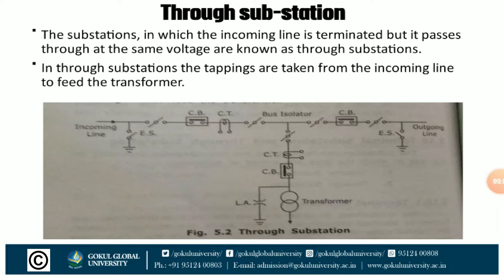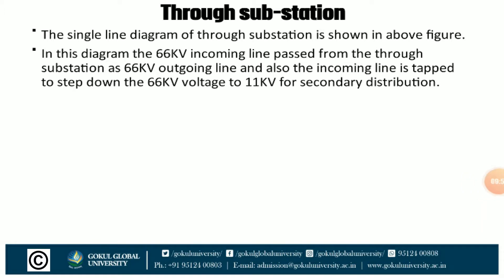Now we discuss about the through substation. The substation in which the incoming line is terminated but passes through at the same voltage is known as the through substation. In a through substation, tappings are taken from the incoming line to feed the transformer. In the single line diagram of the through substation, the 66 kV incoming line is stepped down to 11 kV for secondary distribution.